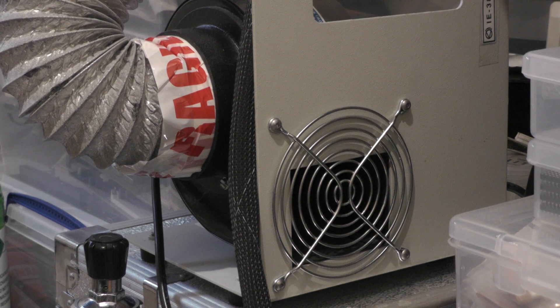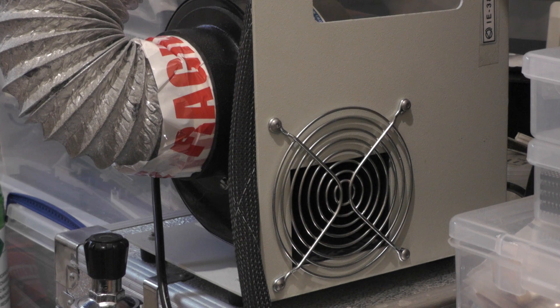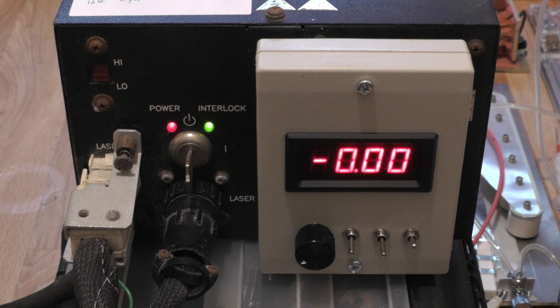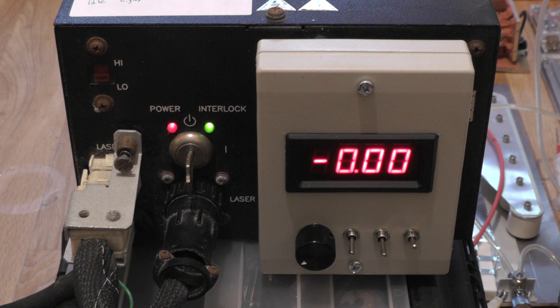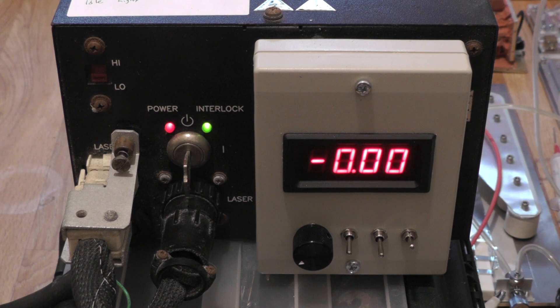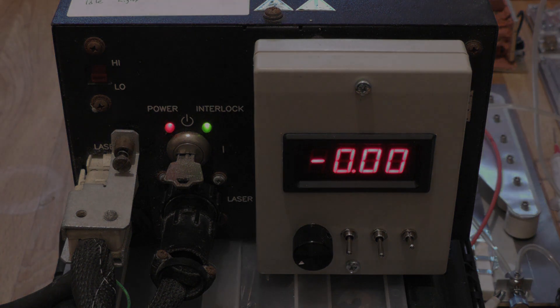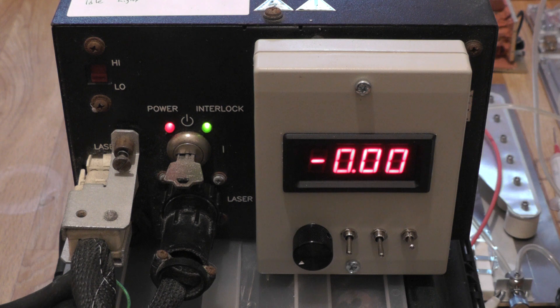So there's the fan on and I'll switch back to the power supply and we'll turn the laser on. So we've got all the cooling fans running now so we'll turn the key and wait and see if the argon laser starts up. You just have to be patient, there's like a 10 second delay. And there we are we've got current.